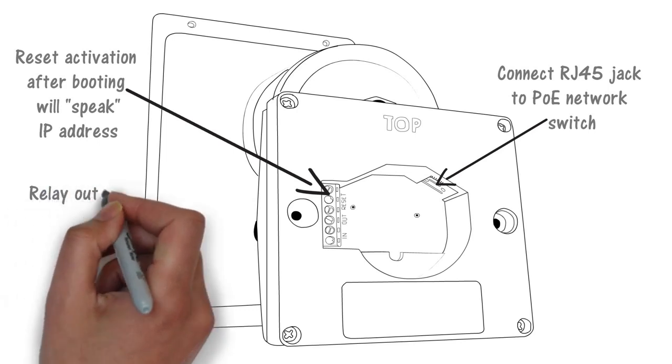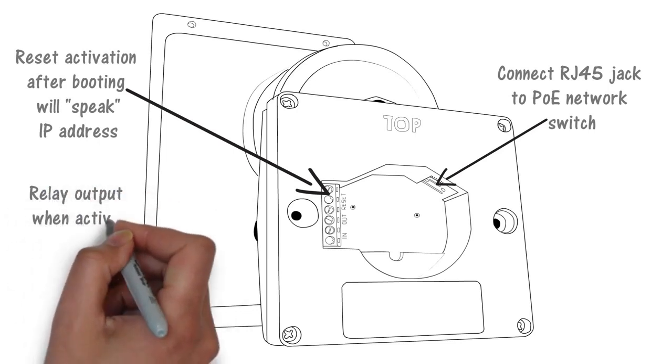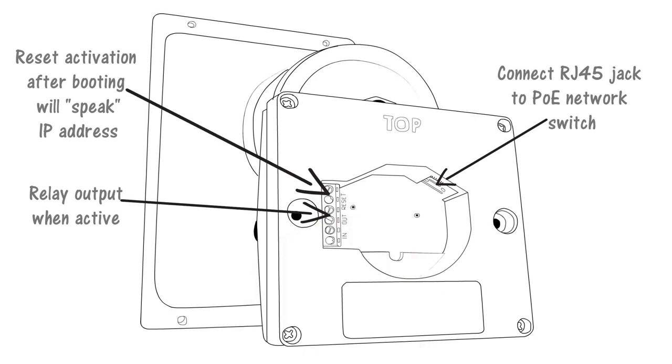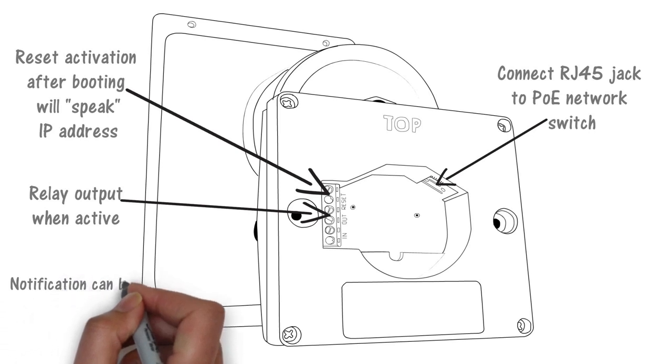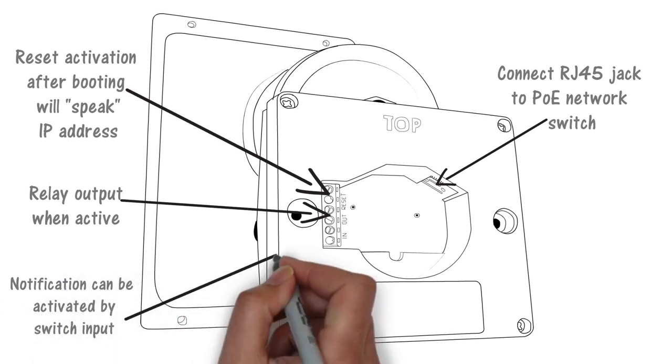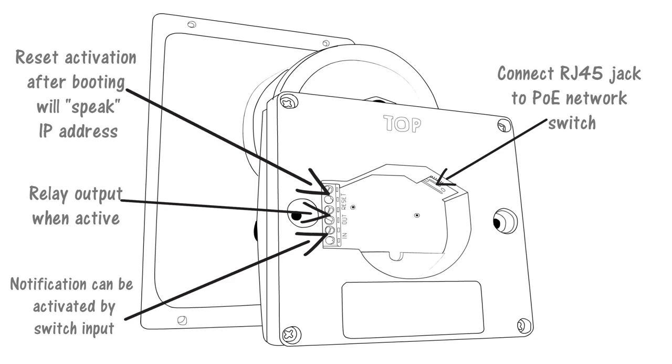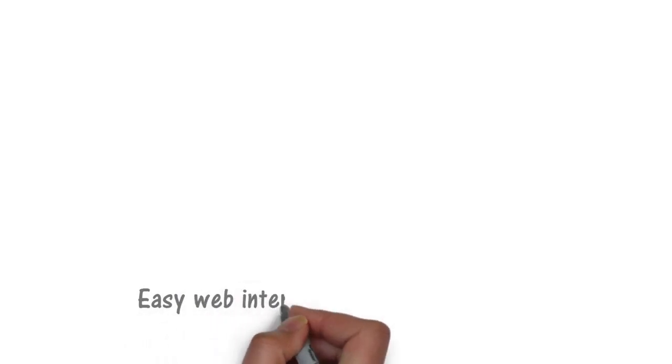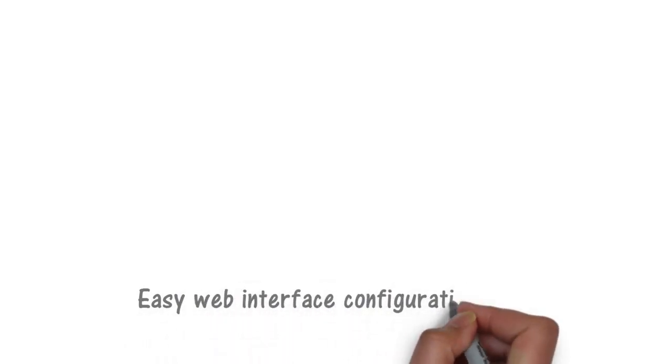A programmable relay output can be used to activate additional alerting products or mute other audio sources. An input may be used to activate an alerting event from a normally open or normally closed contact. This input also supports a supervised connection to the Algo 1202 or 1203 illuminated buttons. When the speaker input is activated, an alert can play or a SIP call made to a pre-configured extension or hunt group.